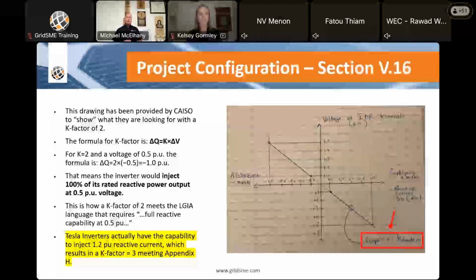The one gotcha that we came across, working very closely with Tesla on several projects, was that, by the way, their inverter is actually capable of greater than 1.0 per unit current injection. And CAISO's model is completely based upon a 1.0 maximum current injection. Because the Tesla inverters have the capability of injecting greater than 1.0, it changed the slope. Once you start injecting proportionally at 0.9 per unit, going down to 0.5 or below, you had to have a different slope. And so we actually have a different slope for Tesla.